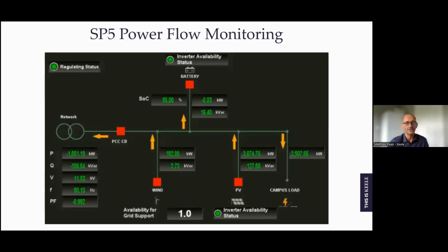To handle that, we've got sub-1-second monitoring in SEND to constantly monitor that export. If we breach that limit to the national grid for more than 5 seconds, they will trip remote breakers in the substation at the renewable site. We lose generation on the wind turbines, solar panels and battery, everything goes off, and it takes around half an hour to reset all those devices and get them generating again. So we do everything we can to stop breaching that limit.